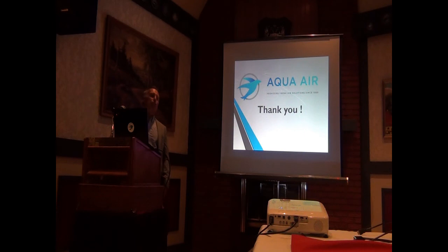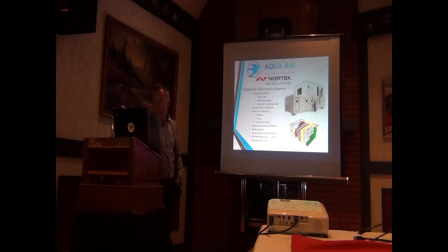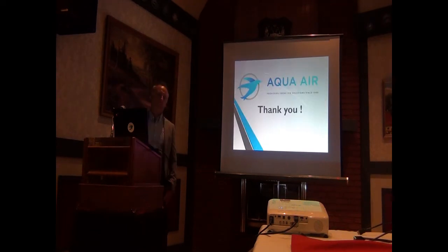You could go to 2. You're seeing a lot more. It scales out of economy. Fan wall maintenance is typically more expensive. Belts have to be bigger, replaced. And then you actually get a lot of savings on size, the footprint. Yeah. And that's how basically an air handling unit, the bigger the footprint, the more cost it is.